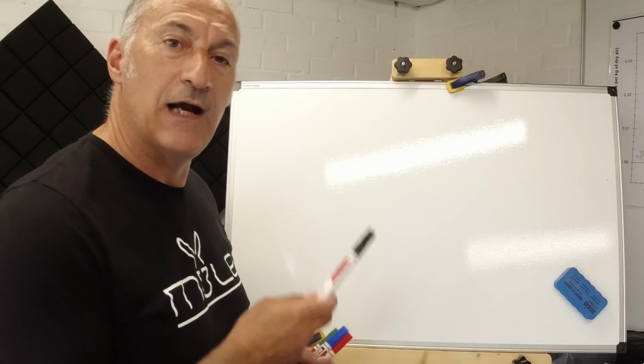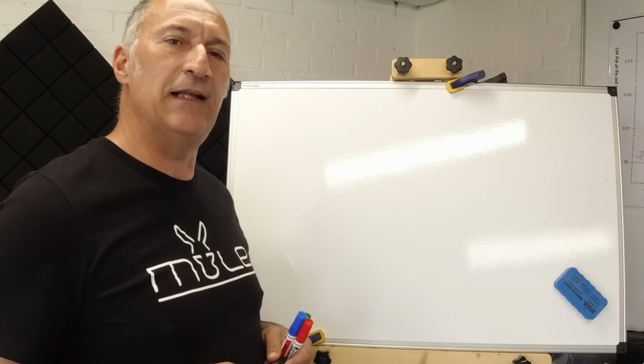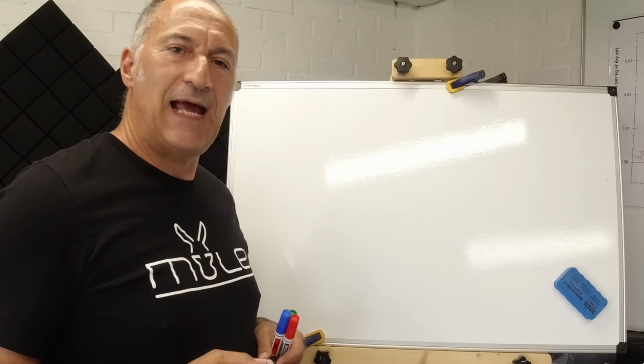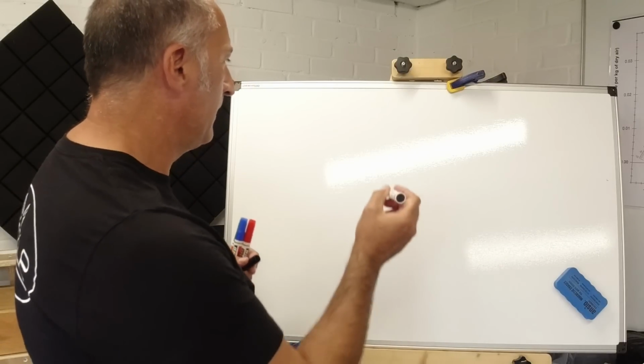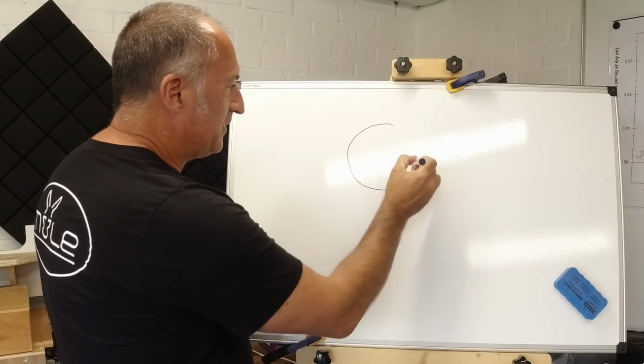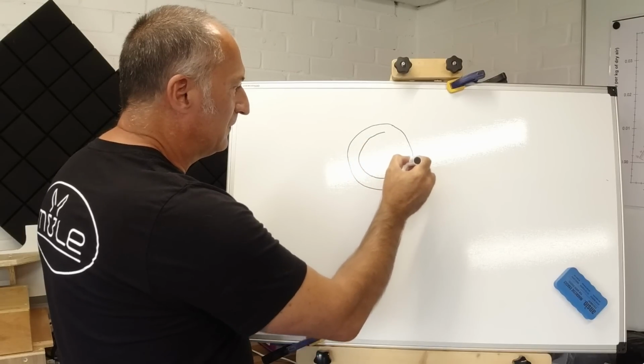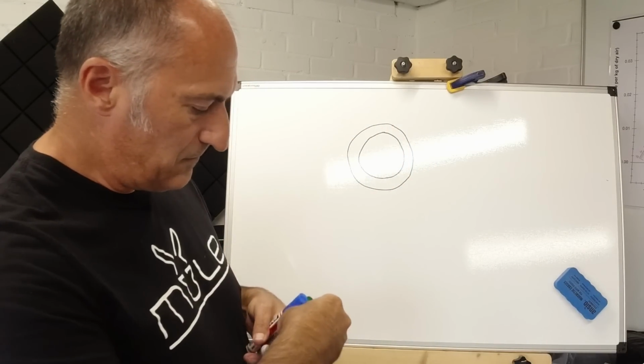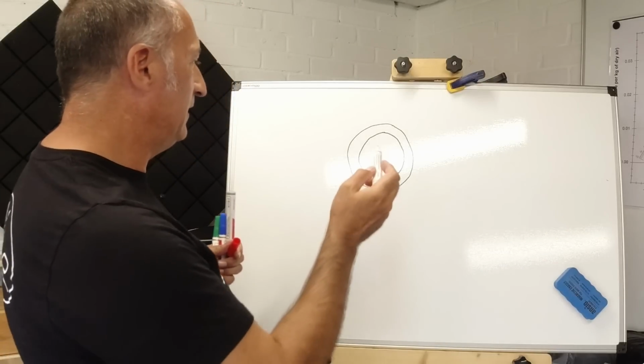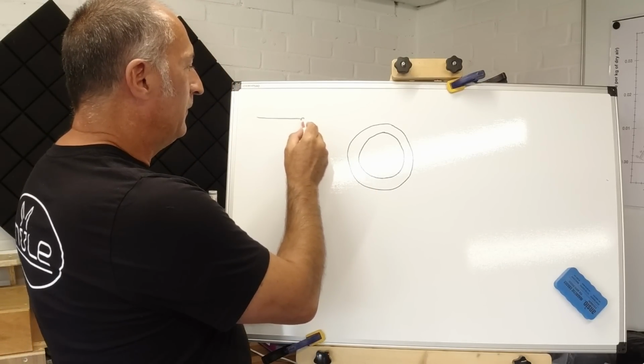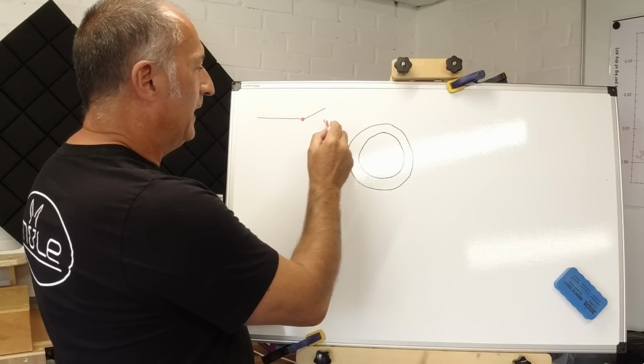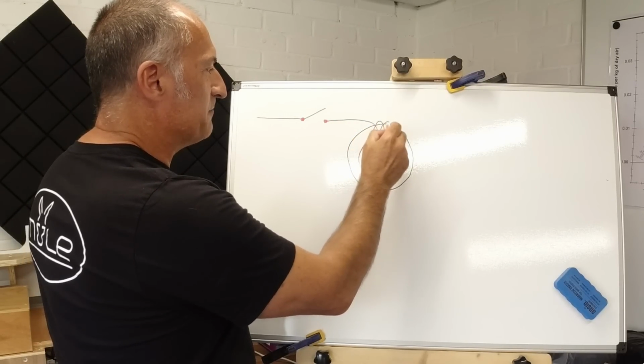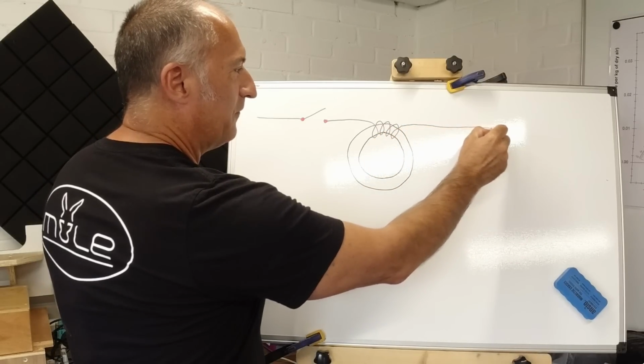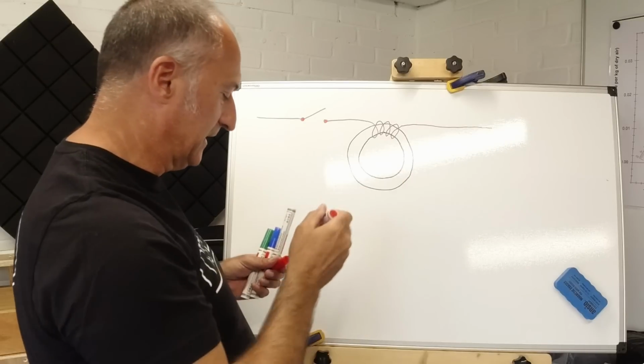So let's just have a look at what the RCD is and how does it protect us. I'm just going to draw a simple line diagram on the board here to represent what's happening inside that RCD so we can better understand how it operates. Inside the RCD is a circular metal core. We'll have our line live conductor coming into the RCD via a switch internally, and then that line conductor will be wrapped around this metal core, and then that will go off out to our load or our device that's connected to it.